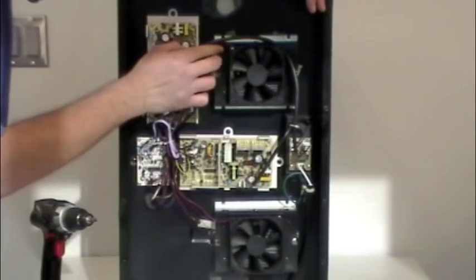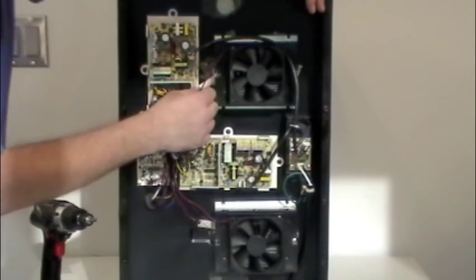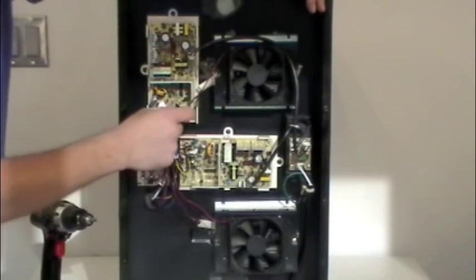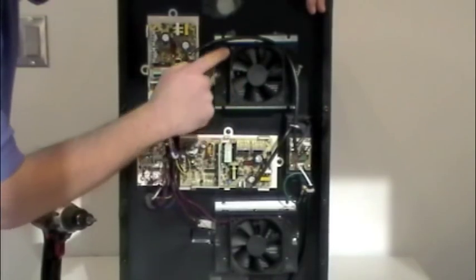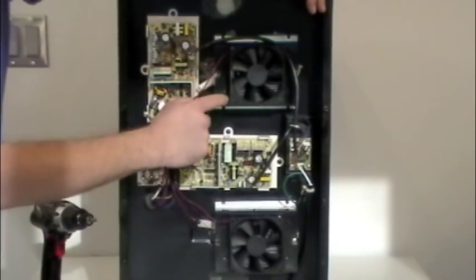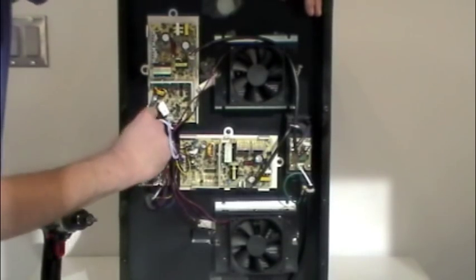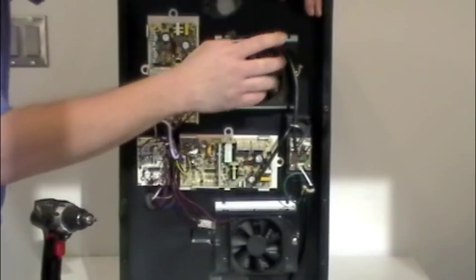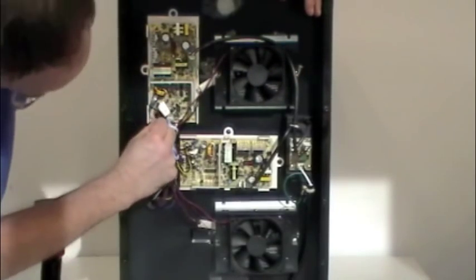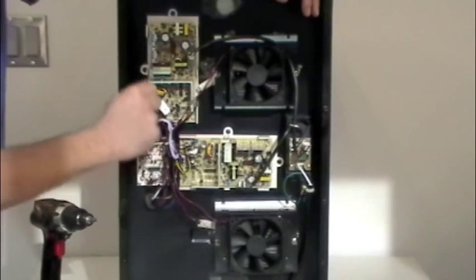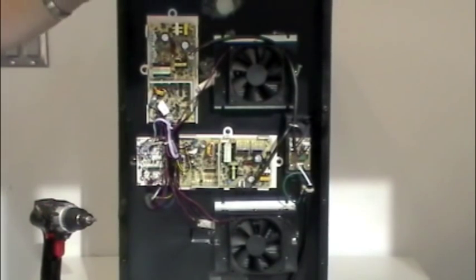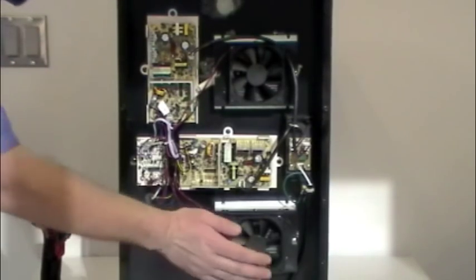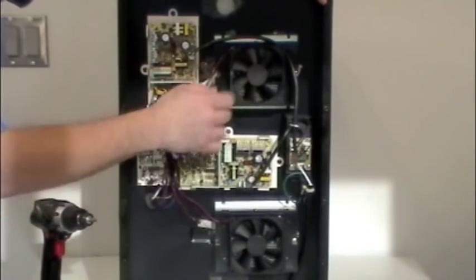If you have an infinity situation where the fan just doesn't have any resistance, at that point we take the fan out. To get that fan out, basically all you need to do is you're going to clip your bundle here, disconnect your wire from the board here, and you're going to come and take these four screws out. There's a screw in each corner and then that whole fan just backs out of there. To replace it, you put the screws back in with the new fan and then come over here and plug in our connector for our fans. And this other one here works exactly the same way. Again, these boards are identical. So when I refer to one board, I'm actually referring to both. So the procedure is the same.